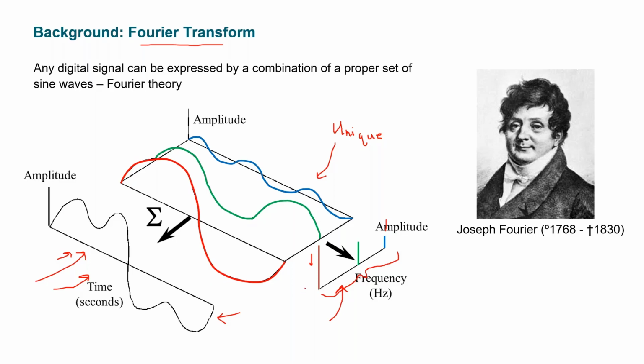And I always joke, it's very useful. We know who to blame for a given noise or vibration problem. We can see, like, 60 hertz is really big. I know that's the compressor. They're to blame for the problem. The fan, which is running at 180 hertz, that's very low amplitude. I know it's not to blame. So I pick on the compressor person and not on the fan person, for example.